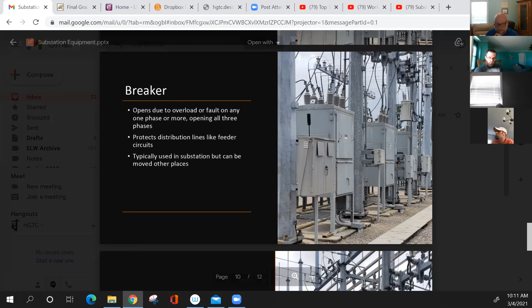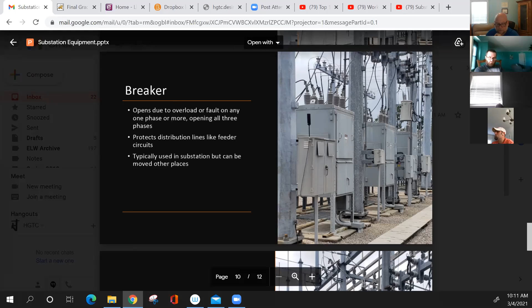Okay. And you want to make sure you got all your PPE on when you're going into this, because you've got stuff you have to check on inside these doors and possibly take this panel out, and you can see how close to the ground you're standing. I mean, you're just within a couple feet of these hot primaries coming off that bus bar. So make sure you have all your PPE on before you go into this sub.